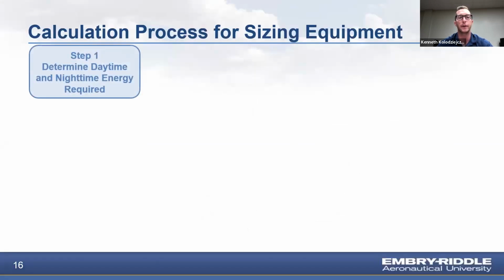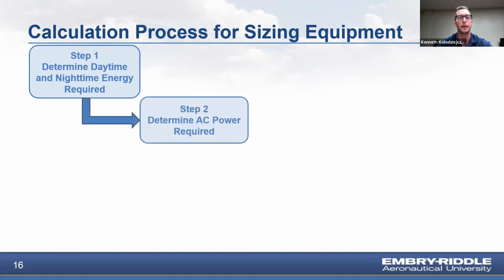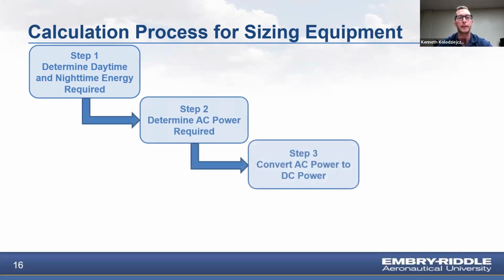Sizing the amount of equipment for each building began with determining the amount of daytime and nighttime energy required using a MATLAB code. A baseline was set for how much energy would be provided by the grid for each building, and everything over that amount was provided by solar power. The energy was converted to AC power by dividing the daytime and nighttime energy by 5 peak sun hours, since that is the amount of time the energy could be produced. To convert AC power to DC power, the AC power was multiplied by a DC to AC ratio of 1.2, which falls in the range recommended by the Energy Information Administration.